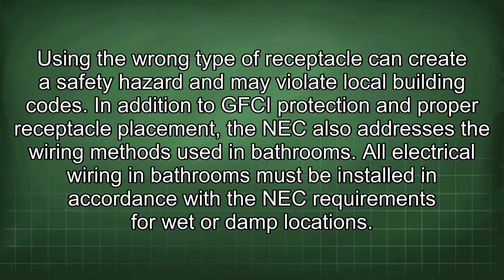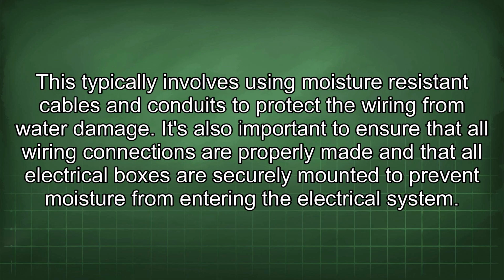In addition to GFCI protection and proper receptacle placement, the NEC also addresses the wiring methods used in bathrooms. All electrical wiring in bathrooms must be installed in accordance with the NEC requirements for wet or damp locations. This typically involves using moisture-resistant cables and conduits to protect the wiring from water damage. It's also important to ensure that all wiring connections are properly made and that all electrical boxes are securely mounted to prevent moisture from entering the electrical system.